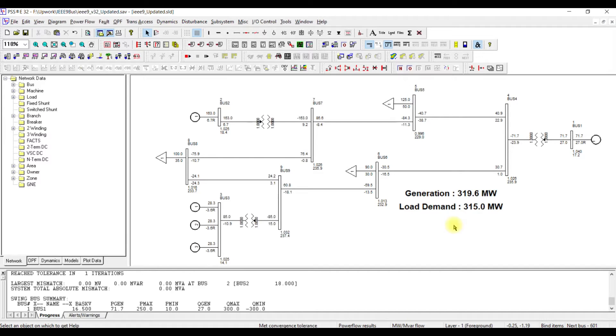If we trip a generator of 28 MW, there will be a deficiency of 28 MW in the system. Generation will drop to 292 MW against a load demand of 315 MW, causing frequency to drop. The frequency change will be affected by two things: first, the total inertia in the system; second, how the frequency recovers depends on the response from each of the remaining generators. To observe these, we need to monitor two types of channels: system frequency and mechanical power input from each generator.